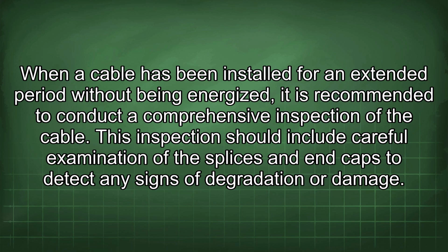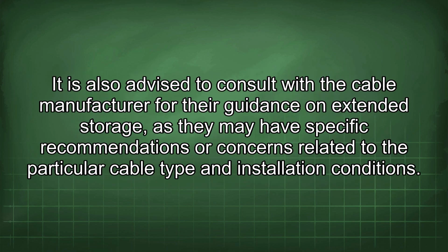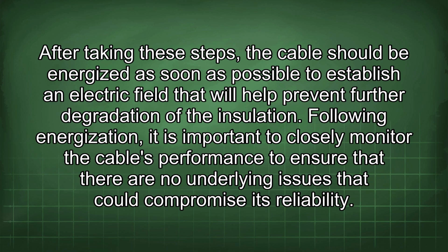When a cable has been installed for an extended period without being energized, it is recommended to conduct a comprehensive inspection of the cable. This inspection should include careful examination of the splices and end caps to detect any signs of degradation or damage. It is also advised to consult with the cable manufacturer for their guidance on extended storage, as they may have specific recommendations or concerns related to the particular cable type and installation conditions. After taking these steps, the cable should be energized as soon as possible to establish an electric field that will help prevent further degradation of the insulation.